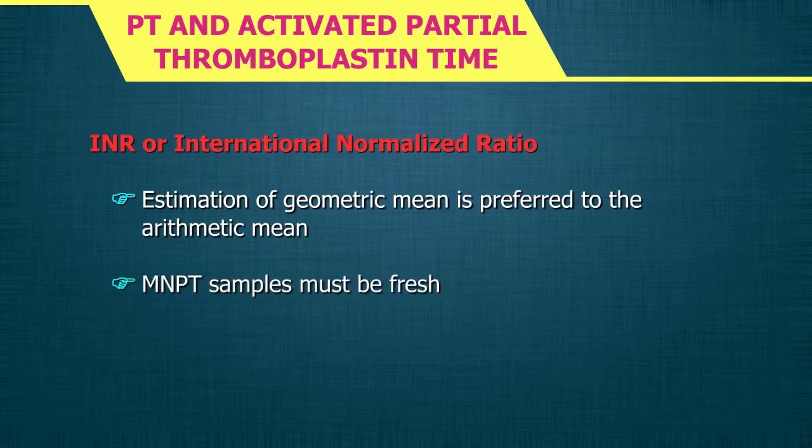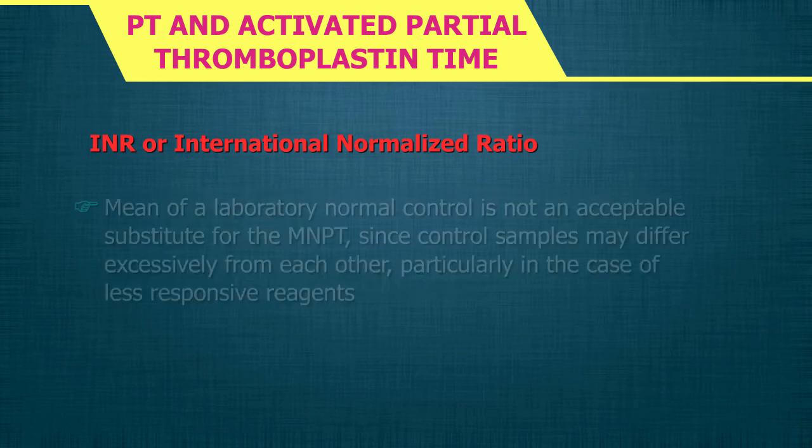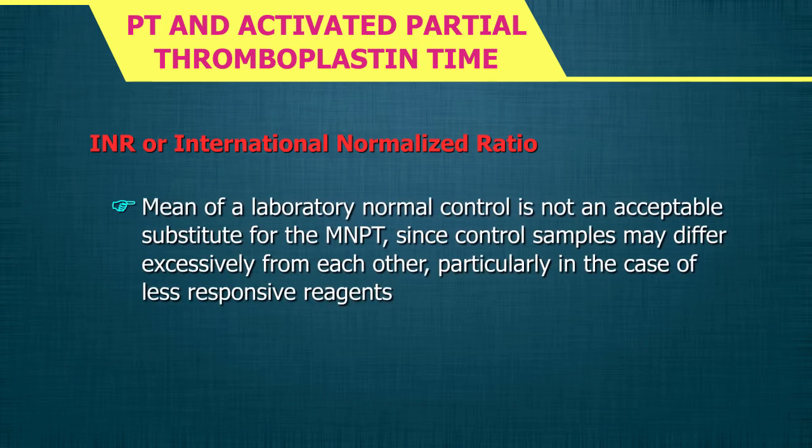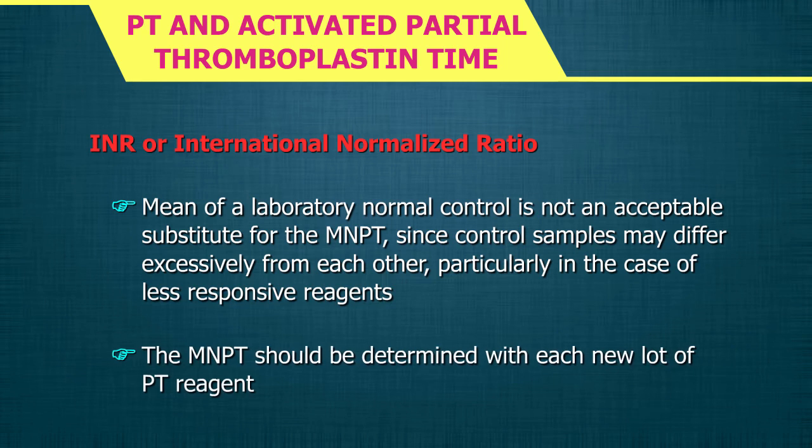MNPT samples must be fresh. The mean of a laboratory normal control is not an acceptable substitute for the MNPT since control samples may differ excessively from each other, particularly in the case of less responsive reagents. The MNPT should be determined with each new lot of PT reagents.